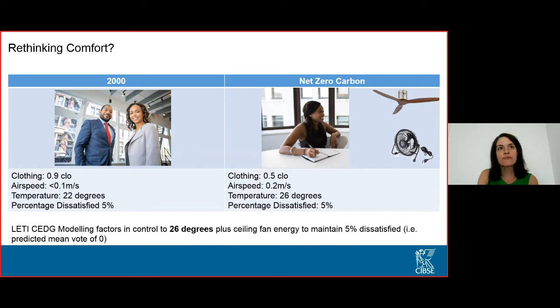So then what if we add a little bit of airspeed and increase the air temperature within the conditioning system to reduce energy? And this is what the Climate Emergency Design Guide posits. So if we can control to 26 degrees and then add a little bit of ceiling fan energy to ensure that we've got a 5% percentage dissatisfied, so a predicted mean vote of 0, that can really deliver some great energy savings.